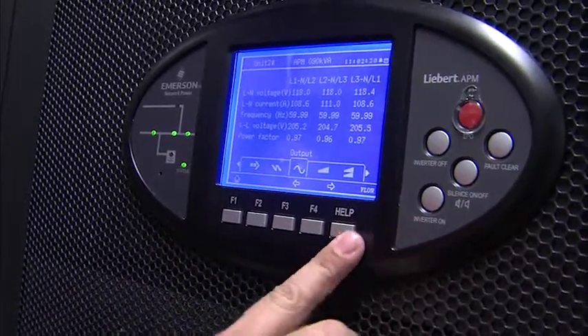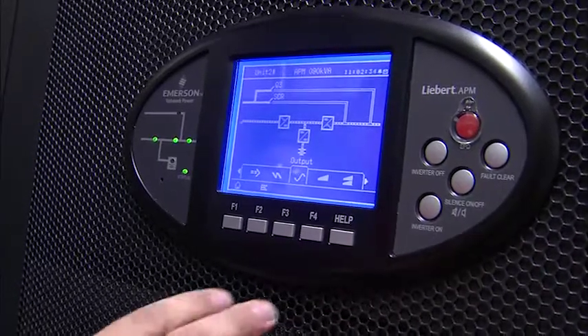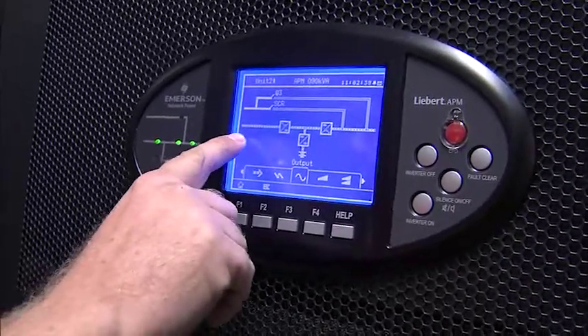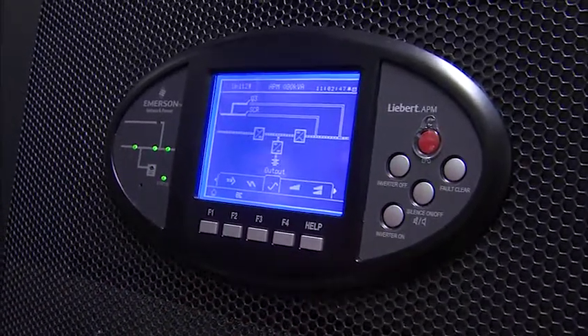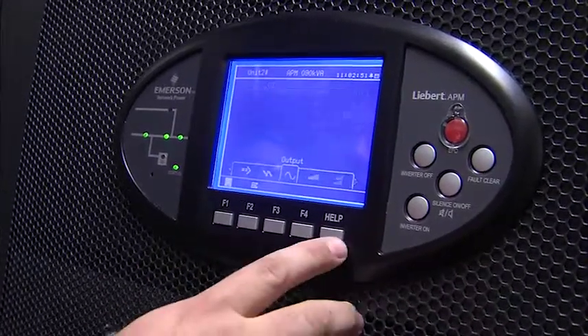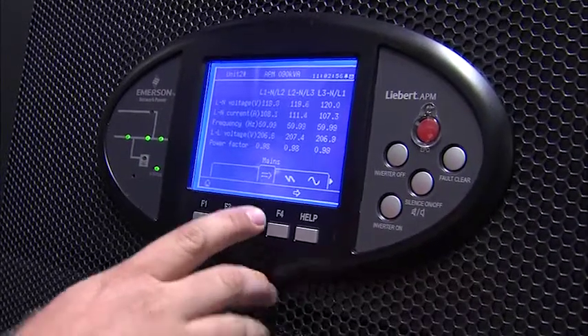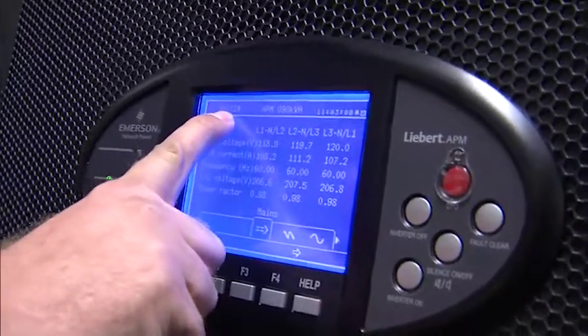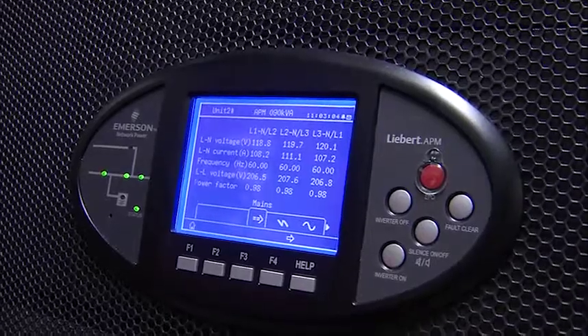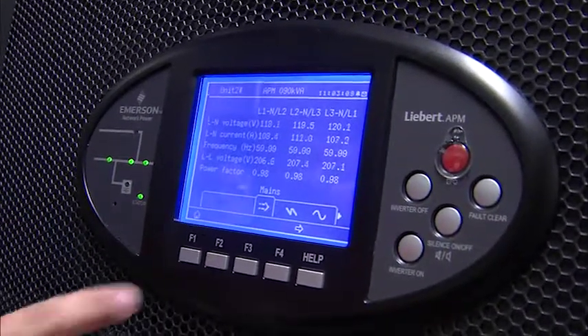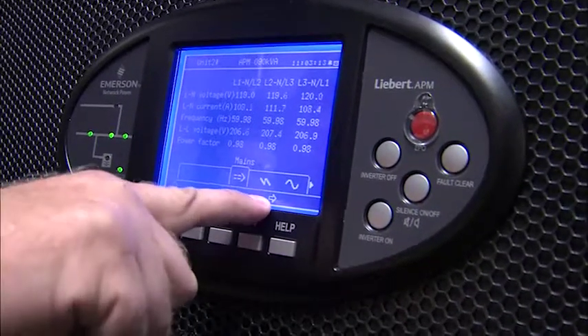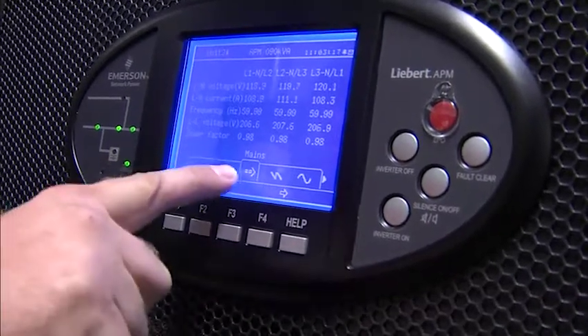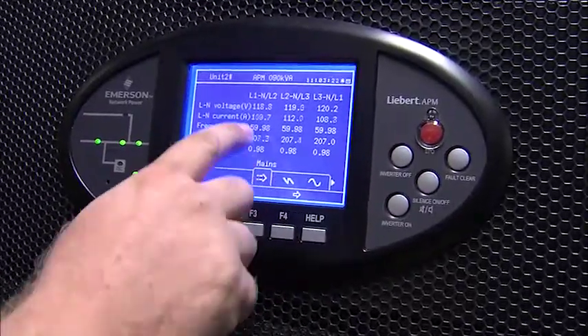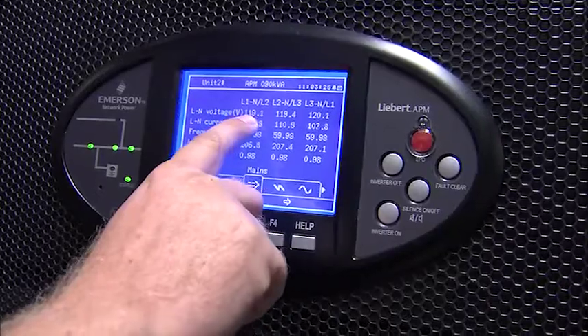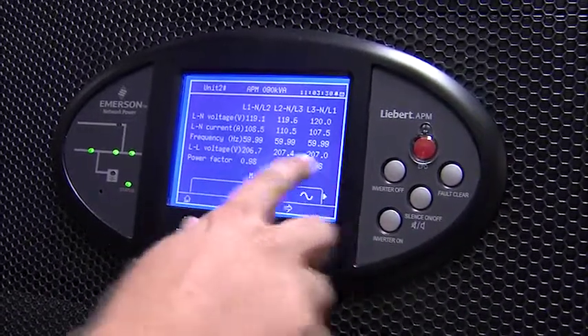Coming down here to these buttons again, that will bring the screen up. And you can push the help button one time once the screen is up, and you can actually see the power flow through the UPS, which is matching this as well. Scrolling through here, you bring this up. This will be labeled unit number 2 on the A side. So down there, that unit will be unit number 1, because they're working parallel. So first screen, as you can see, the arrow coordinates with one of the buttons below. So my first screen is my input, or my main, as they call it. So you can see coming from utility, we have 118, 119, 120 coming in. So utility here is actually really good.